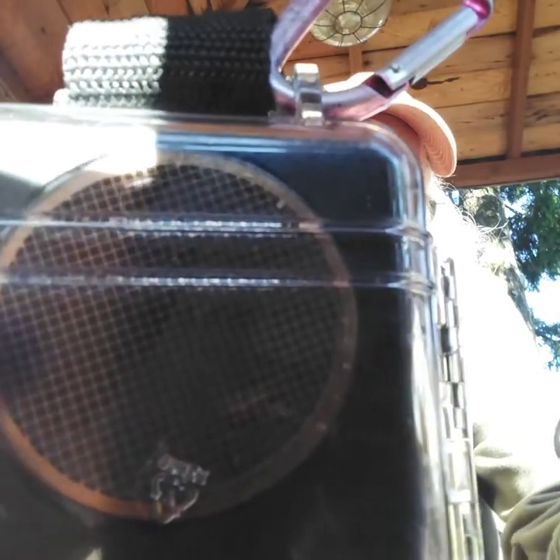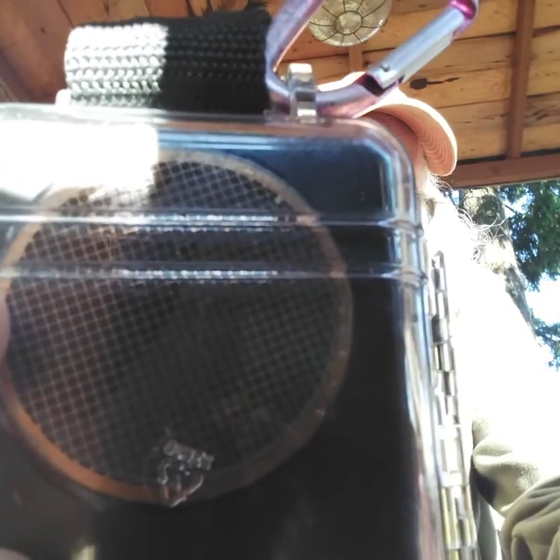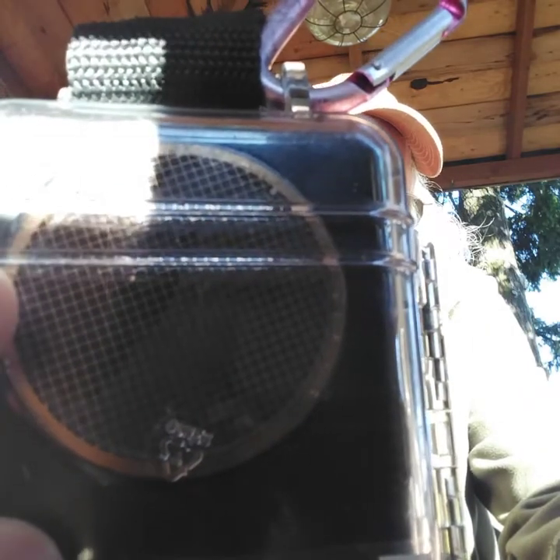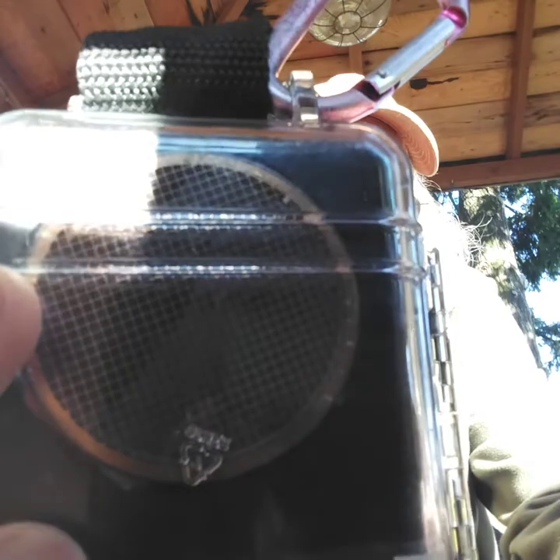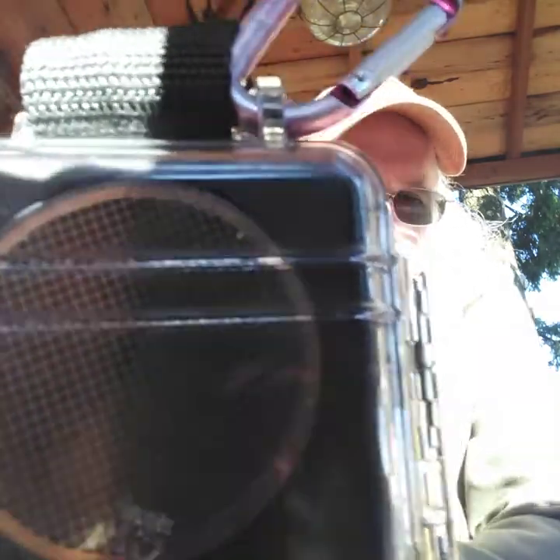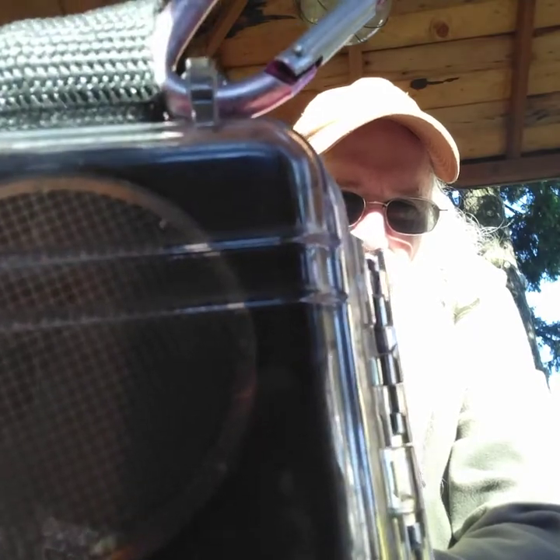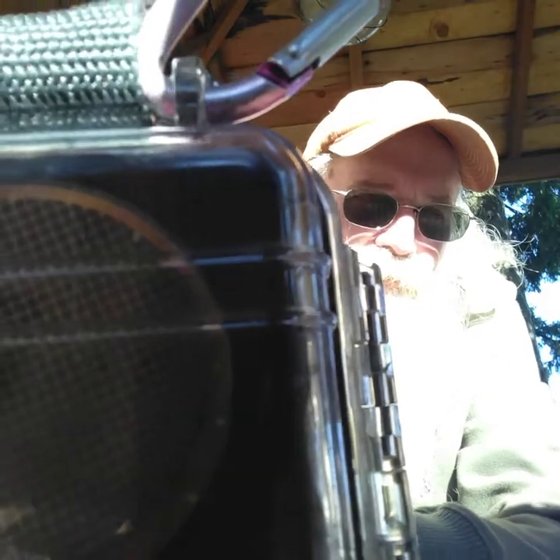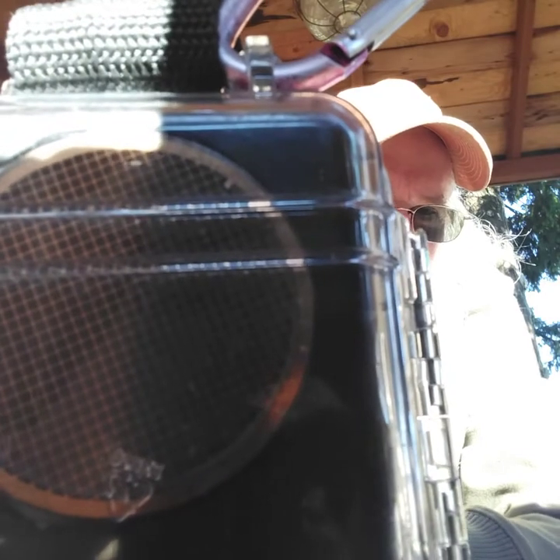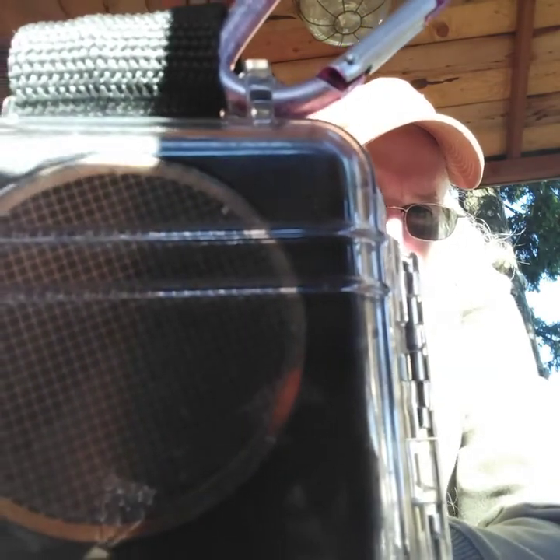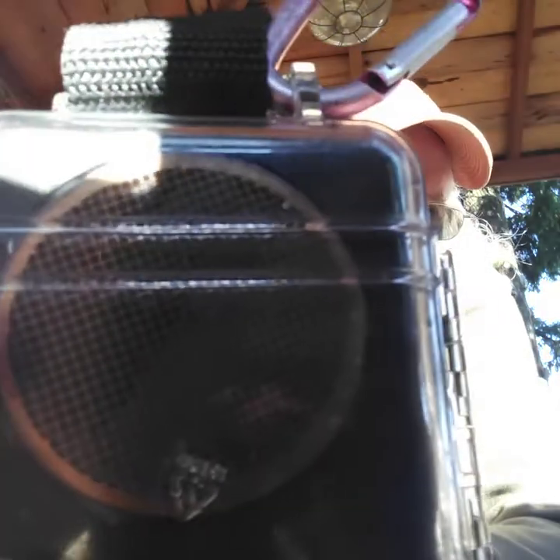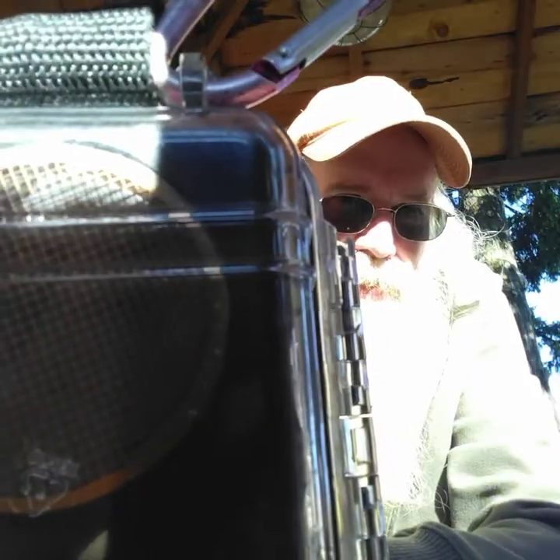This cell phone, it does not detect, even though it's got a transmitter in there for microwave frequencies, right? It's got a Bluetooth transmitter in there on a different frequency, and I'm using it as a headset. So this is a microphone of sorts, but it is only used as a counting circuit. The tube itself has more abilities than that, with more sophisticated electronics and software analytics to go with it. It's a very powerful tube. It also operates at other voltages. It's characterized to operate at other voltages. If I had my druthers, I'd rather have this tube at 700 volts instead of 500.